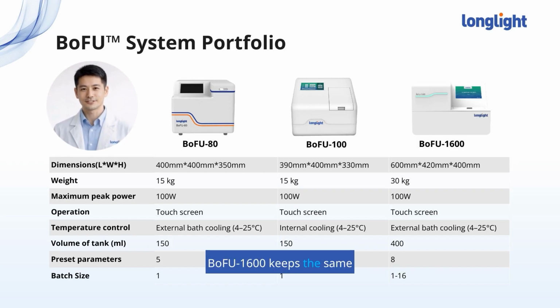BoFU 1600 keeps the same acoustic power but connects to an external recirculating chiller, also 4 to 25 degrees C, and processes 1 to 16 tubes in parallel. This is the natural fit for core labs and sequencing centers that your MGI teams already work with. BoFU 80 also uses an external bath but is tuned for single-sample microbial and pathogen processing, for example upstream of MALDI-TOF or MNGS. All three are 100W systems with a full touchscreen interface. They run as standalone instruments without a control PC or extra software. For your distributors and end users, that means simpler installation, fewer IT issues, and one learning curve across the whole BoFU family.